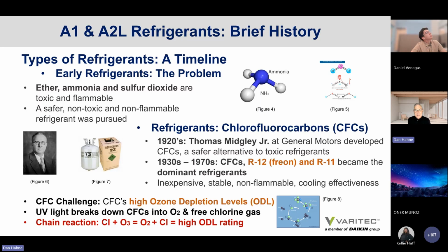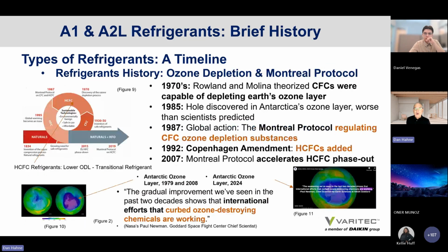R12 Freon is an example of a CFC refrigerant. The CFC challenge is that it has a high ozone depletion level. When a CFC refrigerant is released into the atmosphere, in the upper stratosphere, UV light breaks down the CFC into oxygen, O2, and free chlorine gas. Well, free chlorine gas interacts with ozone to create oxygen and, again, free-floating chlorine gas. So it's a self-perpetuating, self-generating process. Oh, I'm sorry, it has a far deeper impact on the ozone levels within the upper atmosphere.